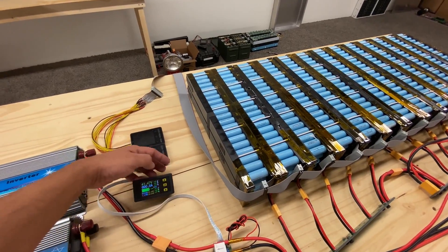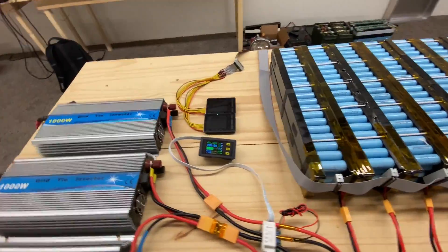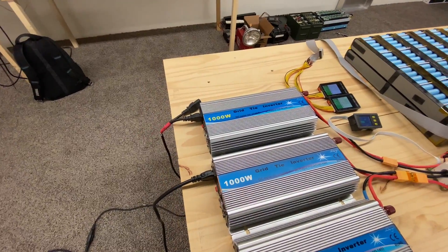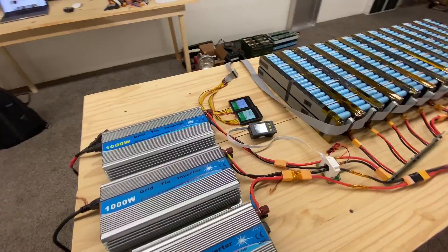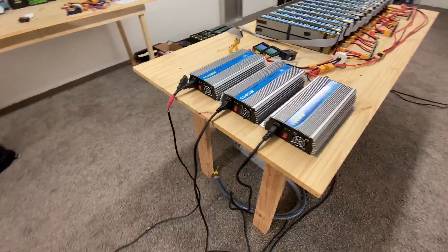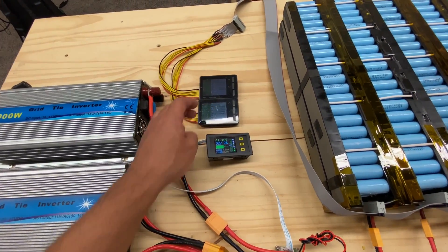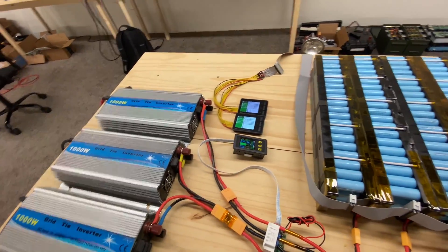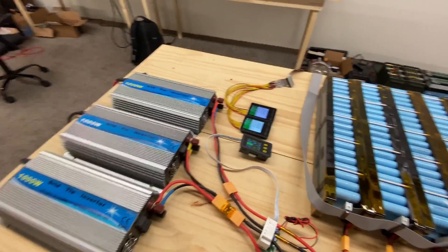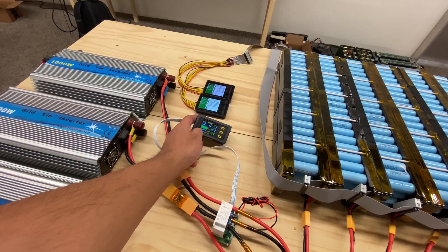Let's do the test. We're at 41.47 volts. Let's start turning these inverters on. Here's the first one — it says run. It's the little indicator saying it's running. There we go, 30 amps. This is a quiet one. The safest load that exists is obviously the grid, so of course we're just dumping all this power into the grid. 29 amps.